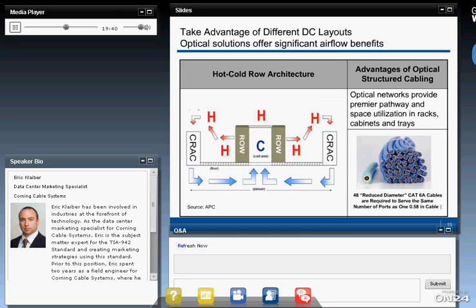In a raised floor environment, the CRAC units send cold air underneath the floor, and it comes up through perforated tiles in what we call the cold aisle. The fronts of the servers all point in towards that cold aisle. They suck in the cold air and blow out hot air. That hot air then gets returned into the CRAC units, whether through an above-ceiling plenum space or just let to wander back. And what we see here is that fiber optics is really an enabler of airflow within these sorts of architectures.